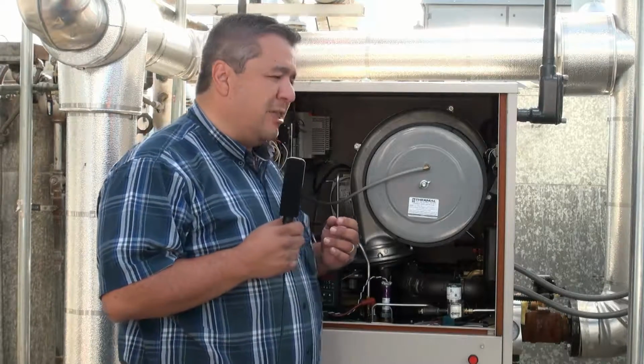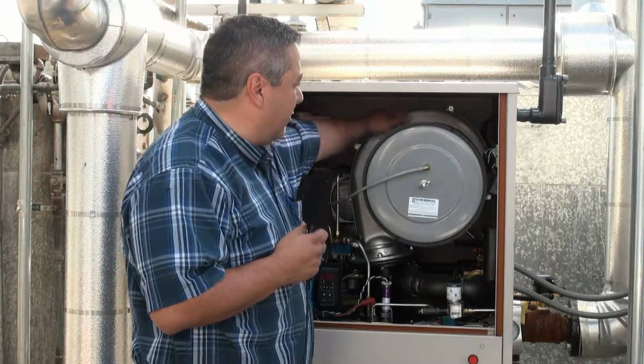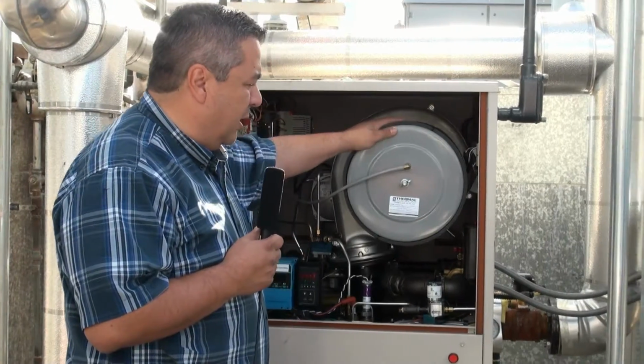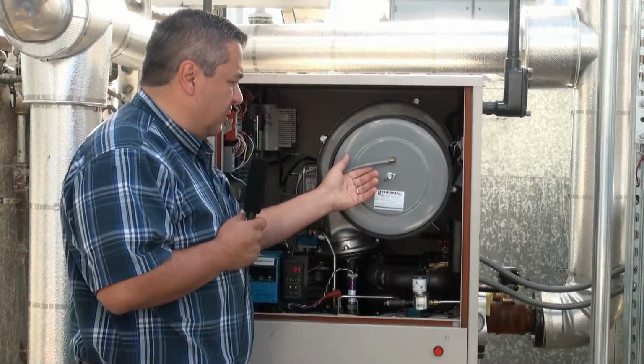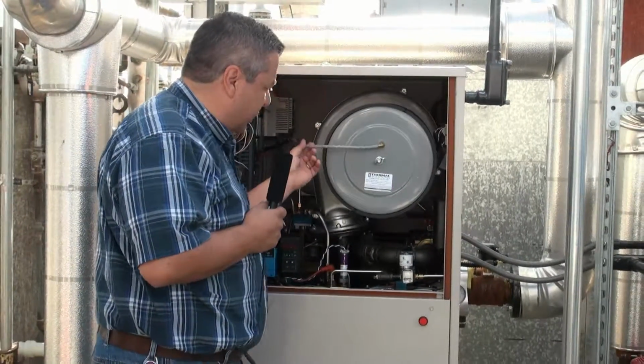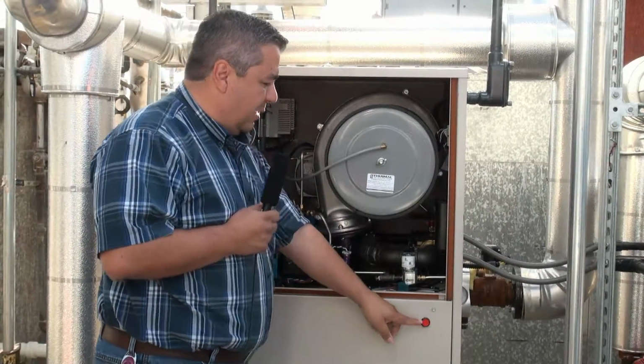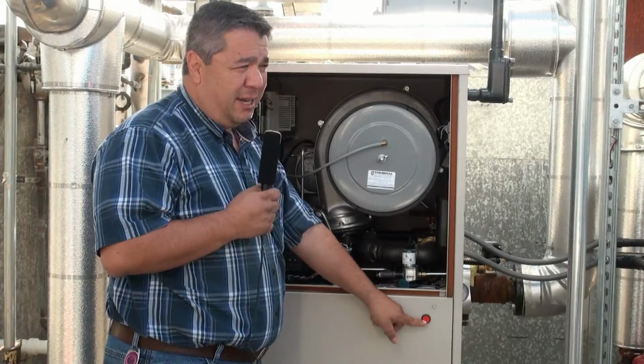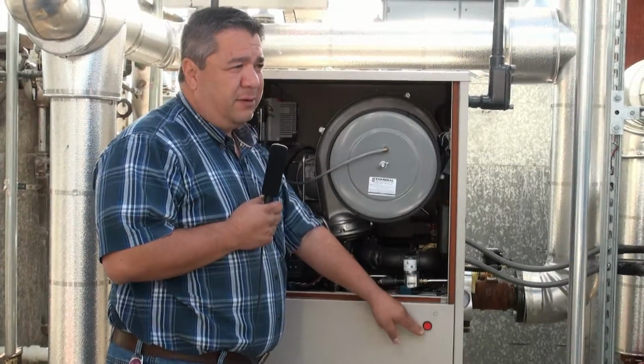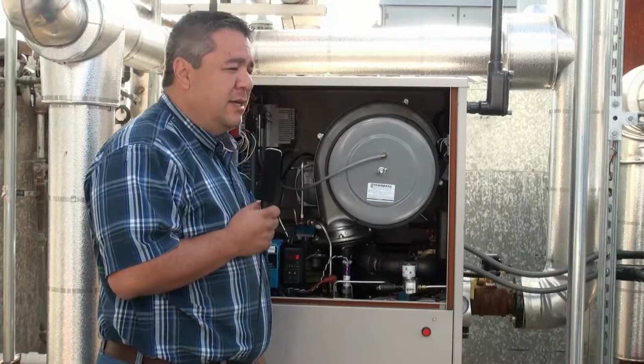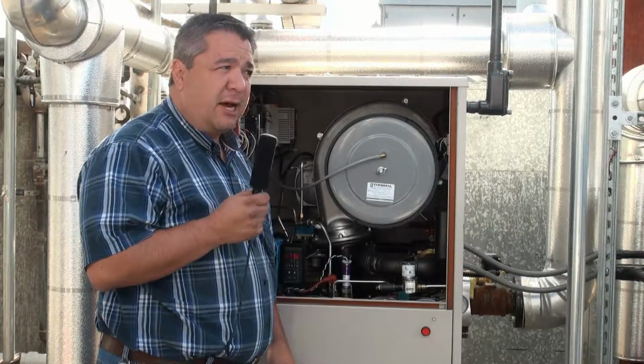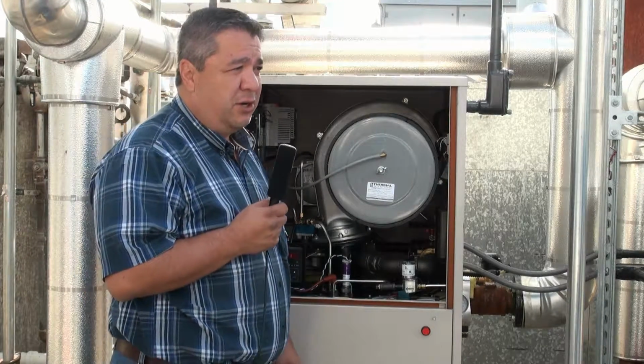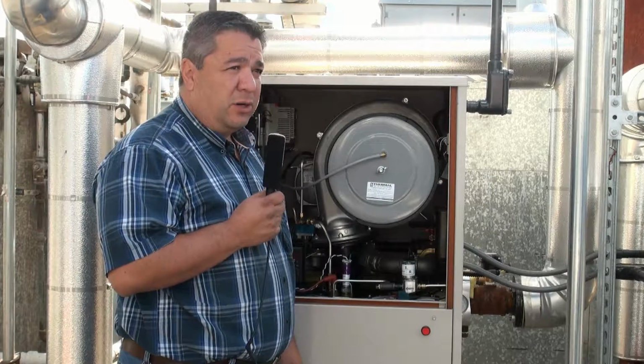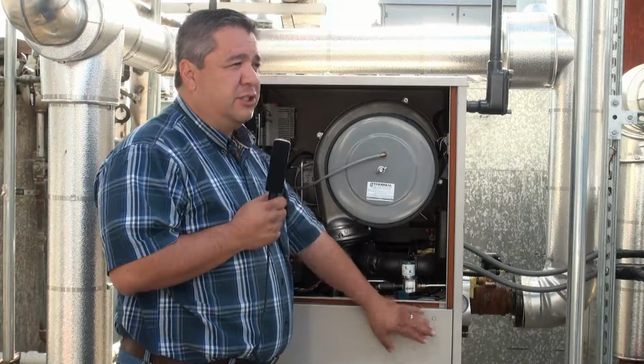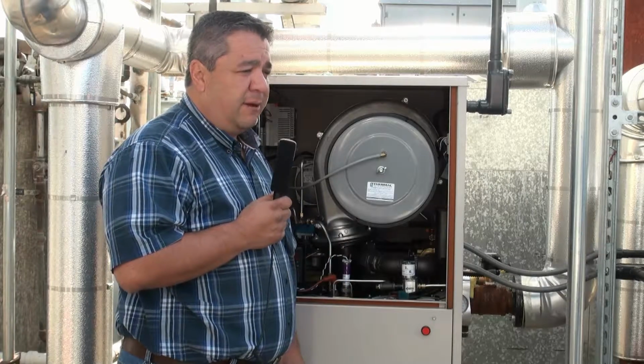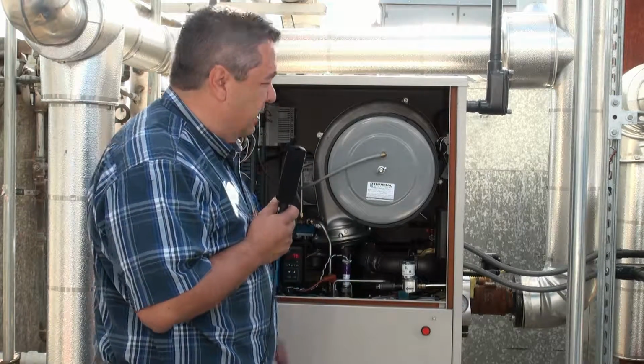Let's talk about the big thing first. This is the blower. We talked about the filter. This little tube here goes back to the filter switch, and it tells you when the filter's dirty. This little light will light red. It's hard to tell in the daytime, but you can get in there and take a look at it. It doesn't stop the boiler from working if that switch is thrown. The boiler will continue to work even if that filter switch's light is on. It's not a safety. It's really easy to change, nothing fancy about it.